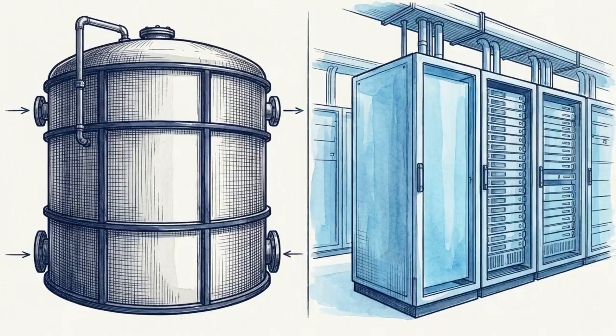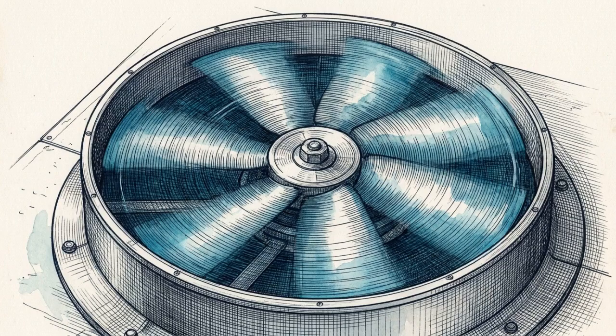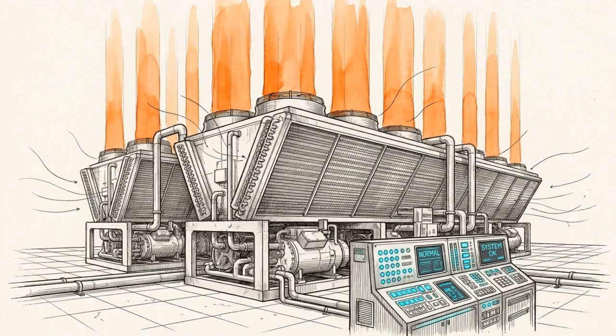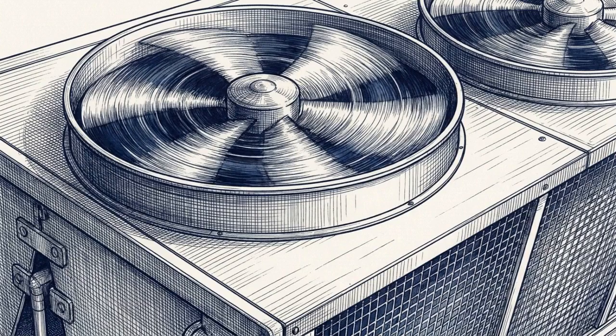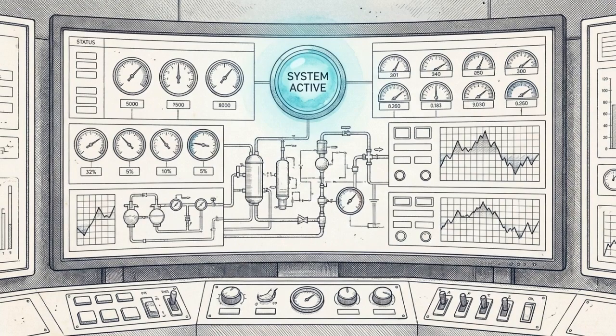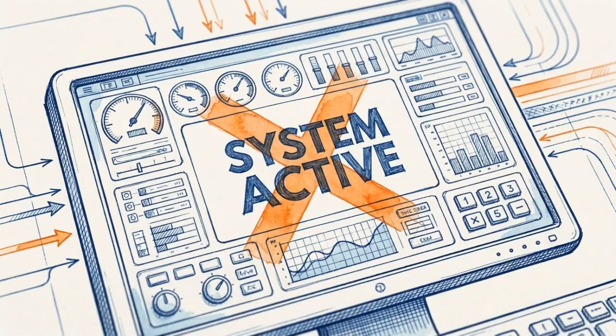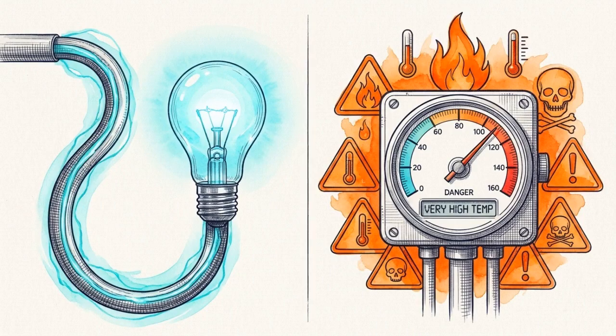The TES tank provides the mathematical certainty to keep the servers alive. It buys the chillers the necessary time to slowly and safely navigate the harsh physical limits of a 40-degree environment without triggering a high-pressure shutdown. At 180 seconds, the chillers are fully spooled up. On a monitor in the control room, the building management system flashes a green indicator confirming the compressors are running. Relying on a Boolean, true or false, run status on a computer screen is a critical operational flaw. A green light confirms electrical current. It is not empirical proof that the plant has actually recovered its capacity to cool.